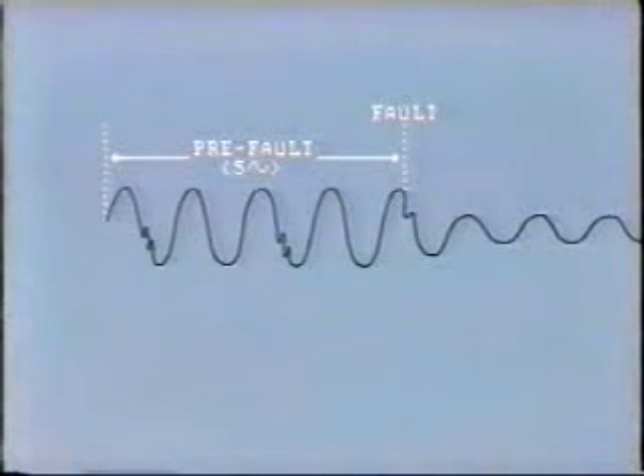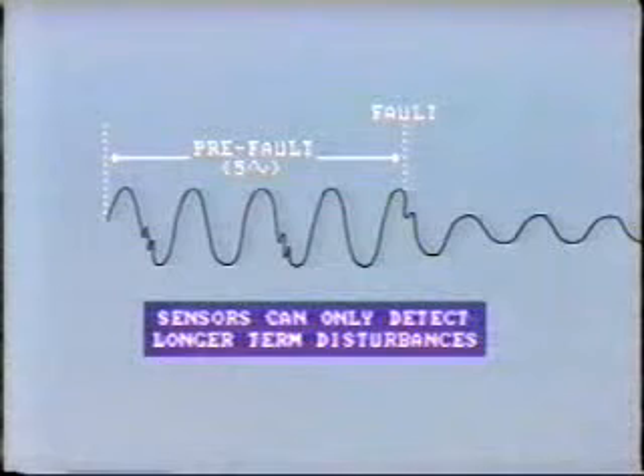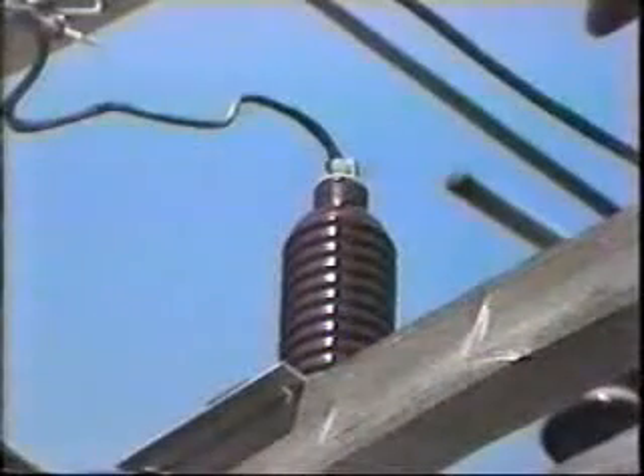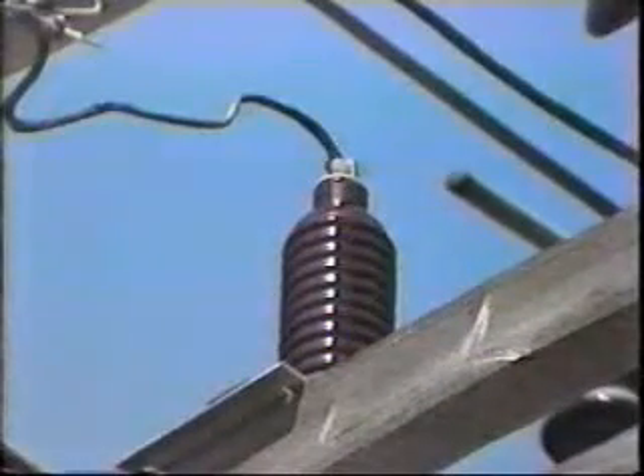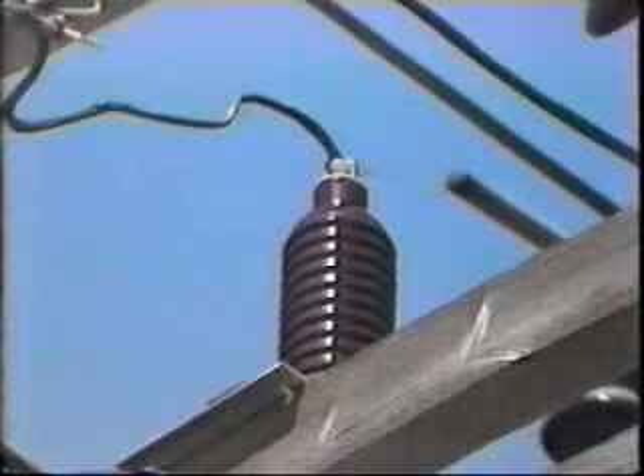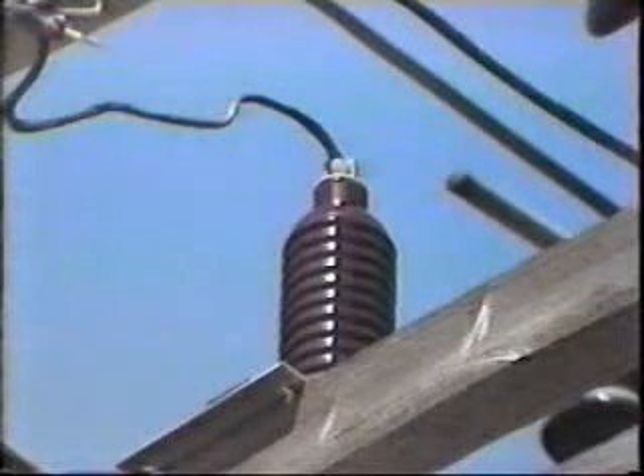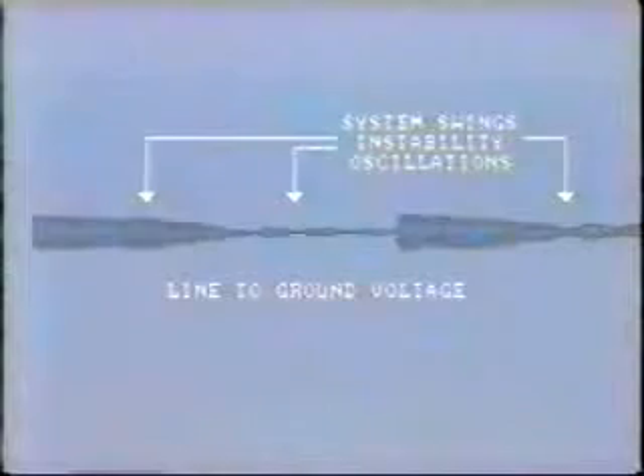But take note, the recording would not have started at all if a fault had not subsequently developed. This is because the sensors can only detect longer-term disturbances in the range of milliseconds or seconds. A normal arrester discharge without a fault is too fast to be picked up by the sensors, so it would not start the recorder. We have been looking at oscillograms associated with faults on the system. Generally, the whole story can be shown within a few cycles, usually less than 1 second.